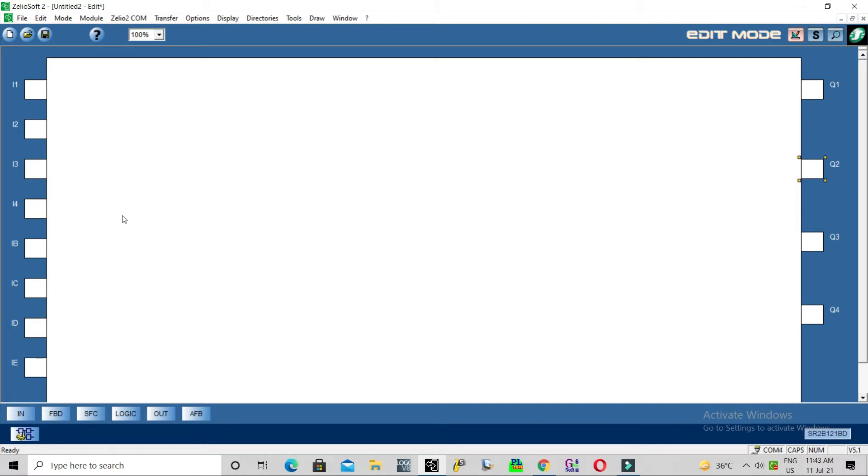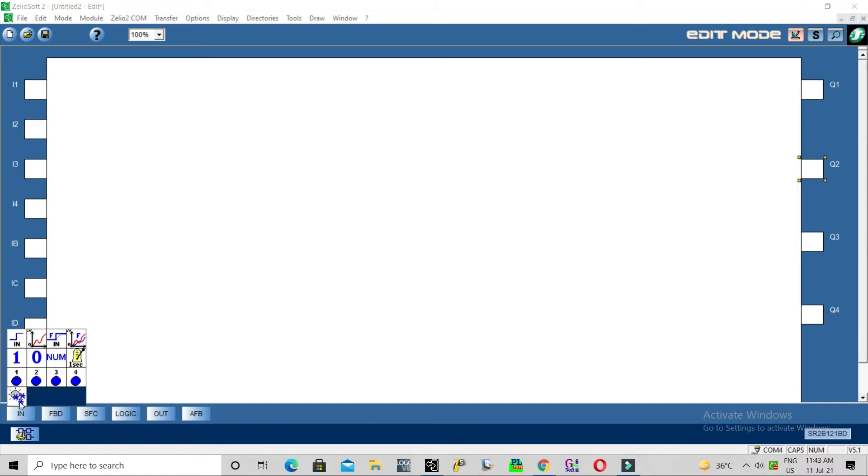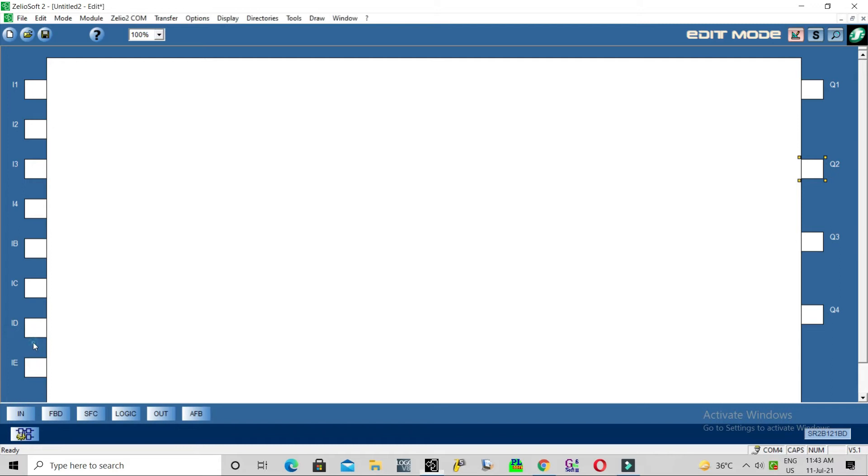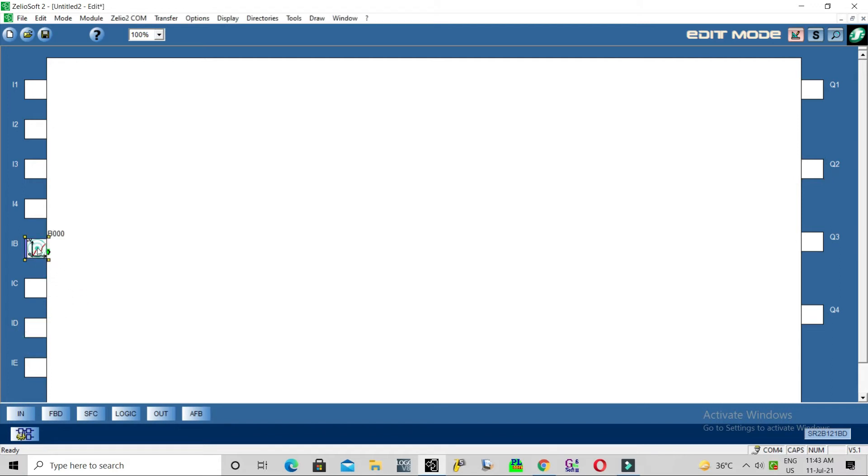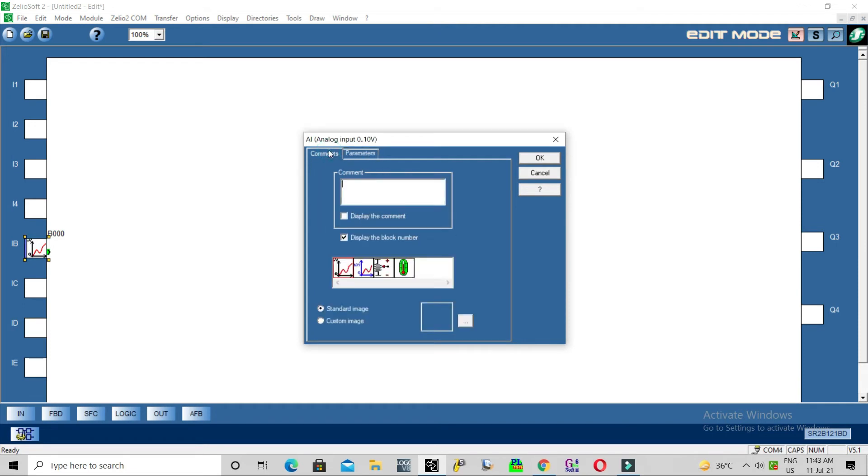Now we'll give analog input 0 to 10 voltage. Basically in this Zelio controller, analog input value is 0 to 255. We will convert this 255 to our requirement - our temperature value is 0 to 100, so we will convert it to 0 to 100.